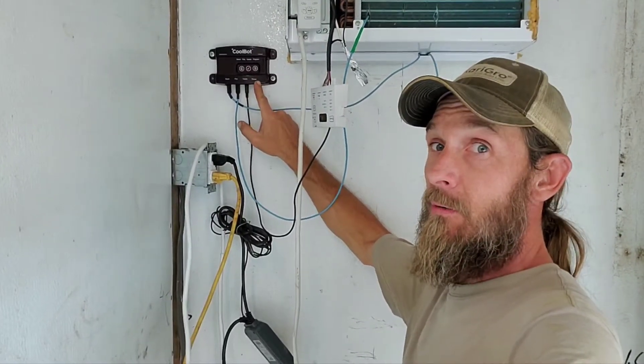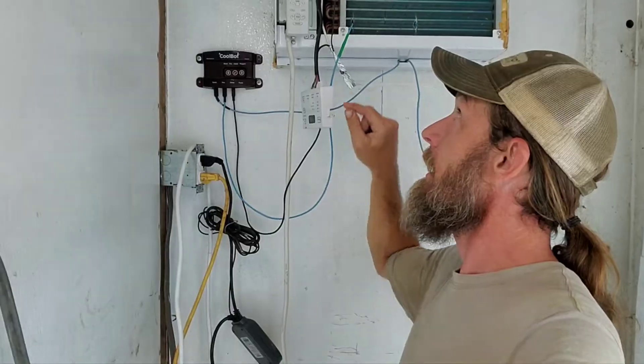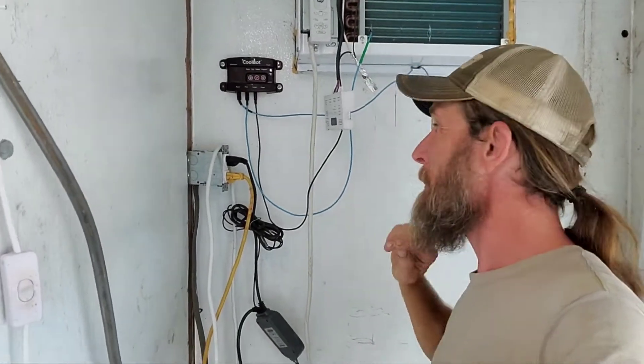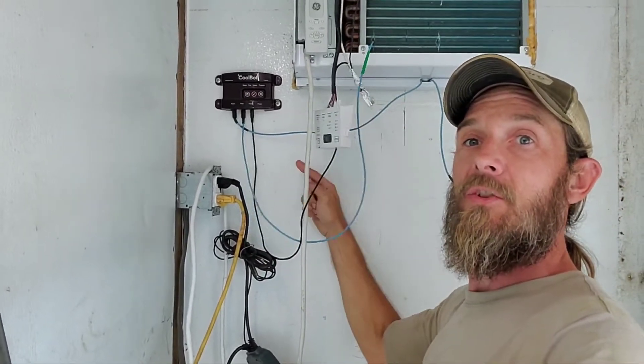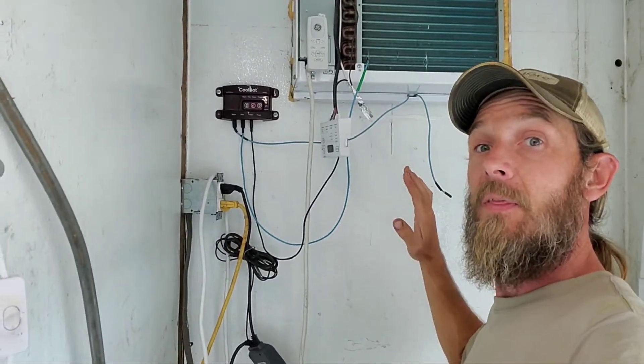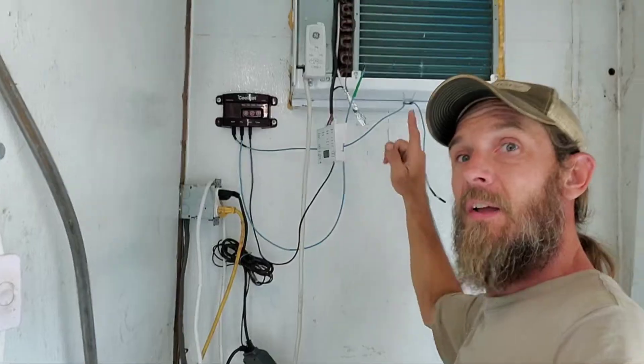Powered by CoolBot. They're cool, but also very expensive. Basically, you hook up the CoolBot, take the sensor off, take its lead, put it here. Snatch the secondary fin sensor out of the back of the unit — these bigger air conditioning units have them. The premise of CoolBot is it has a resistor out here on the end that it triggers, which turns on your temperature sensors. It actually heats up and tricks the air conditioner into thinking it's warmer than it is, which enables it to cool down further. It'll only go to 34 degrees, which nobody needs to go any further — otherwise they start to ice up.